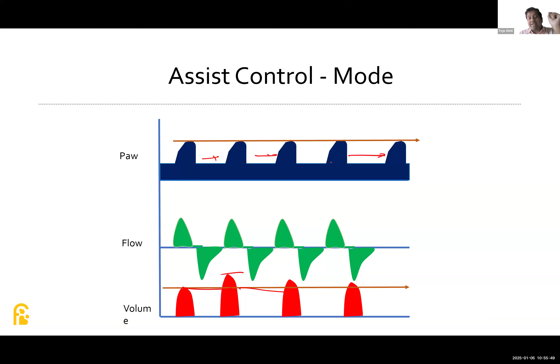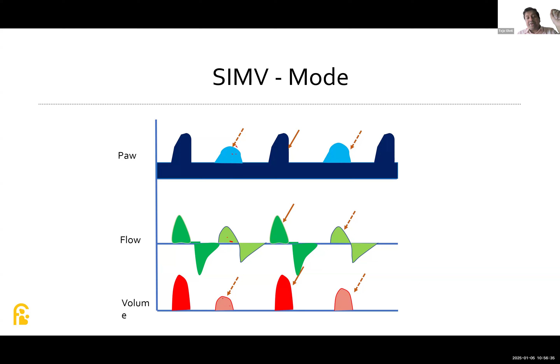Okay, so you can see that the volume is different and there is a little variation in the inspiratory time. If it is a SIMV mode, what is happening here? Some of the breaths are spontaneous breaths and some are machine breaths, if the baby wants to take more than the breaths you have set in the SIMV mode. The sky blue color on the pressure versus time curve is a spontaneous breath, whereas the thick blue is the mechanical breath. So all three parameters, pressure, flow, and volume generated, are different in these breaths compared to the machine breath. That is how you will be able to see it.